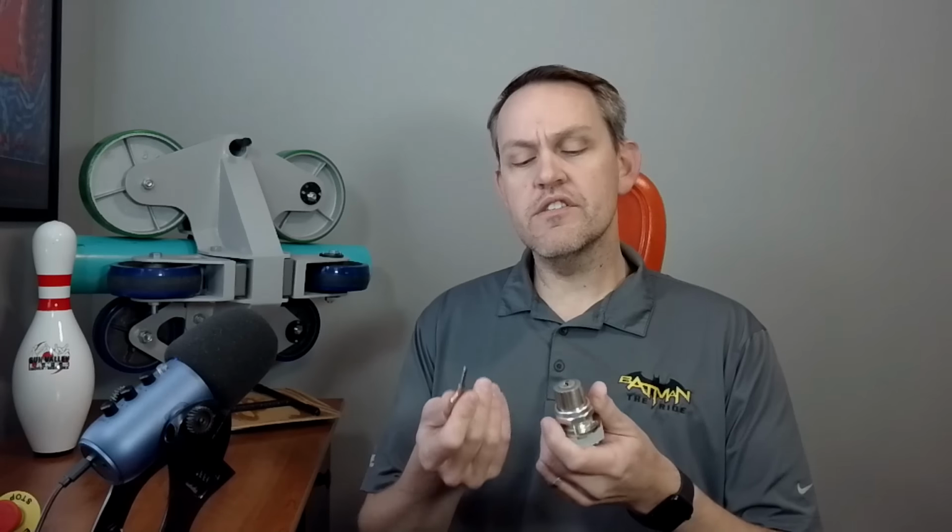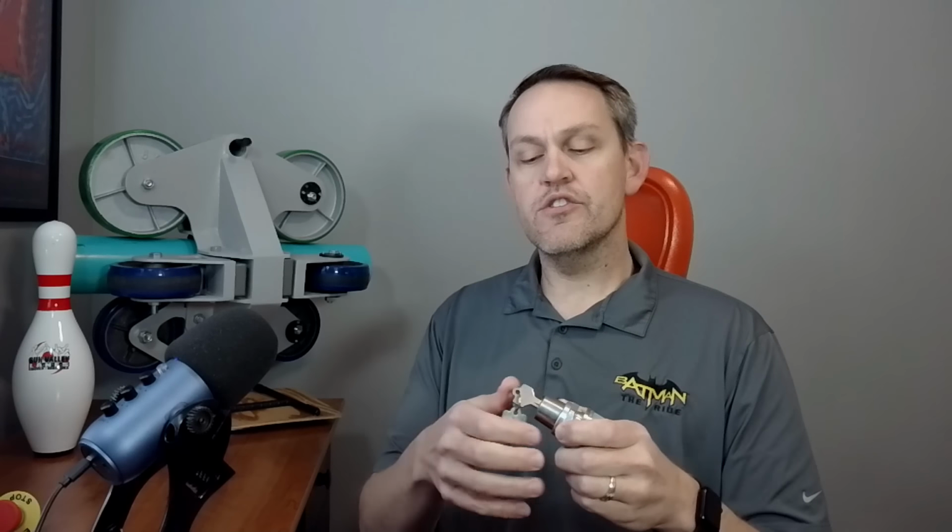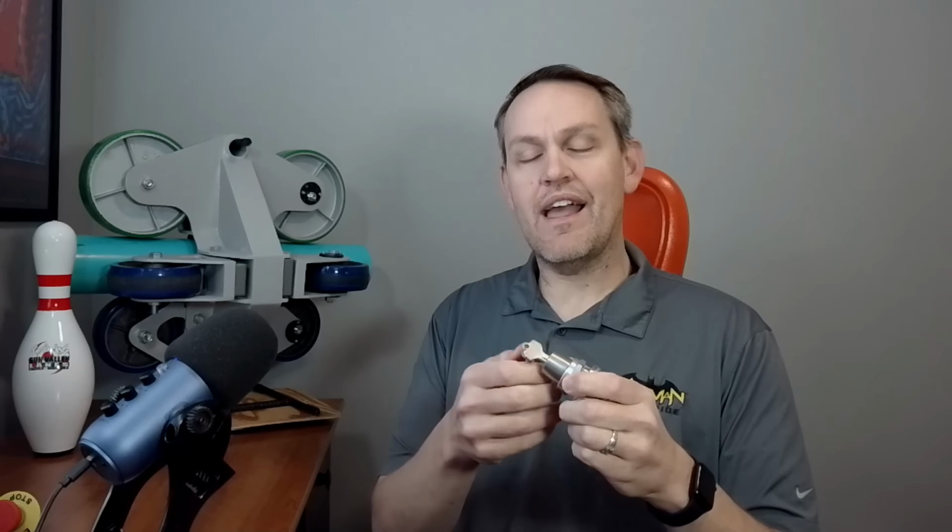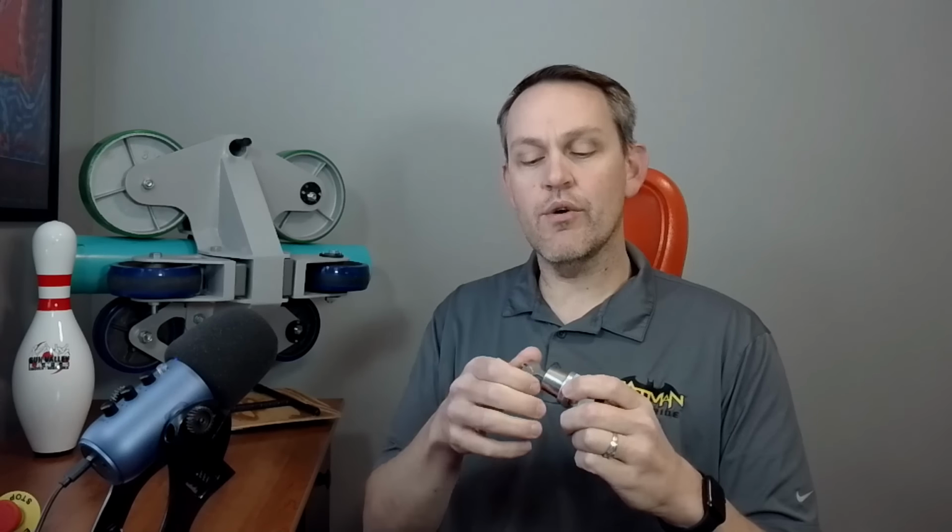But key switches are very important because there's a lot in the key switch that tells you everything about what you're doing. So for instance, this is going to be a maintenance mode type key switch. I put the key in, I turn it, and I can't remove it. So what do I do here? It's like, well, I don't want the maintenance guy walking away and leaving the ride in manual mode. So in order for the maintenance guy to get his key back out, I make it to where it can only be removed in the automatic position. So if I put it in automatic, turn it to manual, and then I try to walk away, I'm like, oh, wait a minute, I can't. My key is there. I need to bring my key back over.